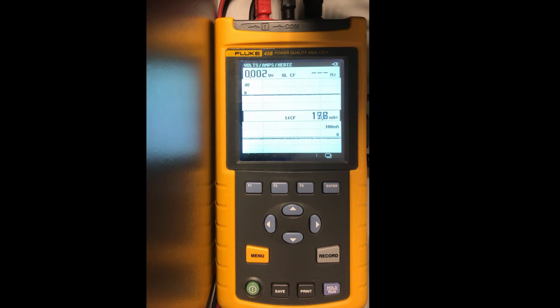Just set it on your bench, and I want to continue to turn that just up a little bit to get it closer to that 0 value. So I'm just giving it little tweaks now to try and get it closer to less than 5 milliamps, right? So you can see now that I'm getting close, and I may have overshot it a little bit, but it looks like I'm able to have it steady out at less than 3 milliamps now. Now, it doesn't mean you have to add 3 milliamps to any of your current readings. It just means that you're properly zeroed as far as this current clamp goes. Okay? So once I've done that, that completes my calibration and setup of the power analyzer.